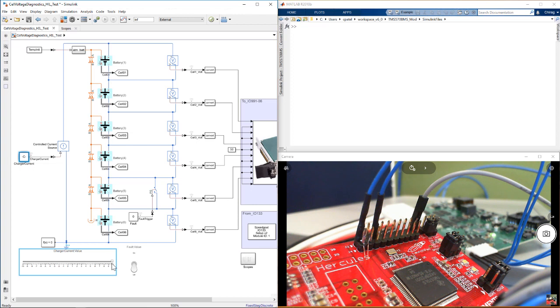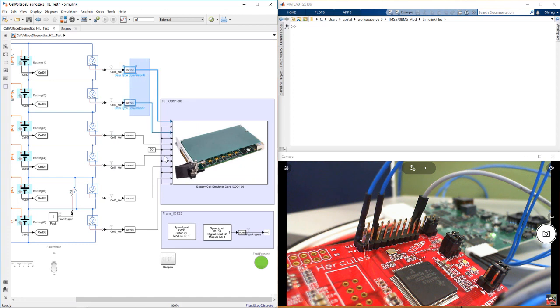To perform diagnostics on the cell, we measure voltage between two cell terminals. The measured cell voltage values are fed into the IO991 block, which converts these numerical values into electrically isolated voltages, each relating to an individual battery cell. The output terminals of the IO991-06 card are connected to an electronics board you see in the background here, which makes physical measurements of the cell voltages and communicates the information to a BMS controller, which in this case is a Texas Instruments controller board.